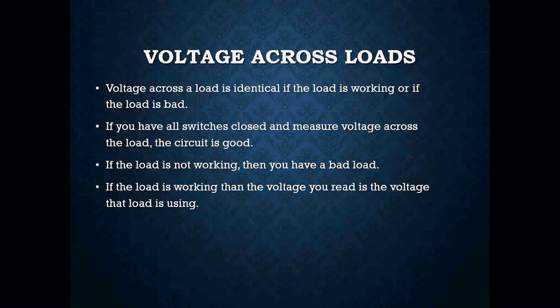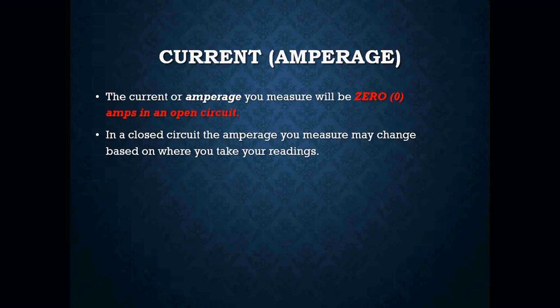Voltage across a load is identical whether the load is working or not. If you have all switches closed and measure voltage across the load, the circuit is good. If the load is not working, then you have a bad load. If the load is working, then the voltage you read is the voltage that load is using. Remember, that is voltage drop. The current or amperage you measure will be 0 amps in an open circuit. If the circuit is closed, the amperage you measure will change based on where you take your readings. The best place to take an amperage reading on any load is as close to it as possible on your neutral wire.